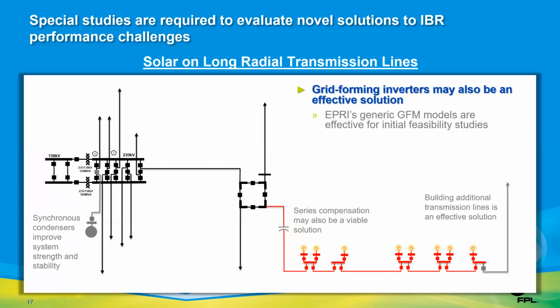Do we require GFM inverters at all eight PV plants, or do we only need them at a subset of those plants? Or is it better to install a standalone battery with GFM controls? And if so, what size should that battery be? Either way, we found that the generic models were very useful in the initial studies just to validate that this was a feasible solution. If we go forward, the next step will be to work with the vendors to require the GFM models for the actual equipment that will be installed, and then we'd repeat these studies.